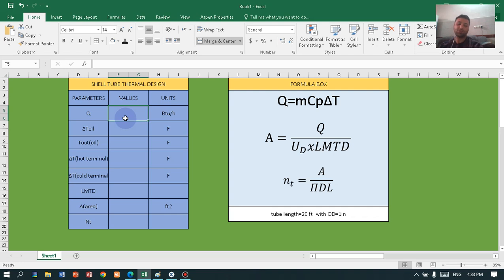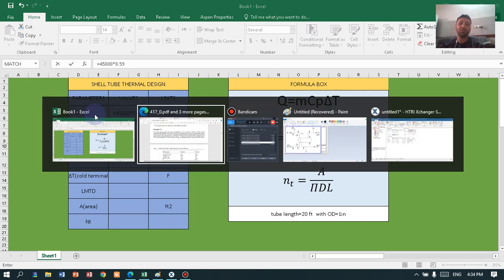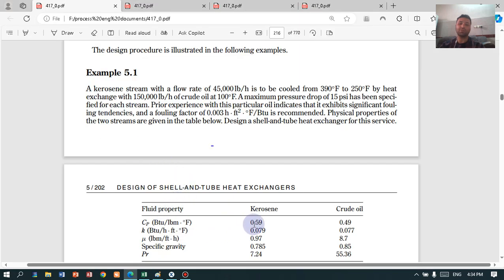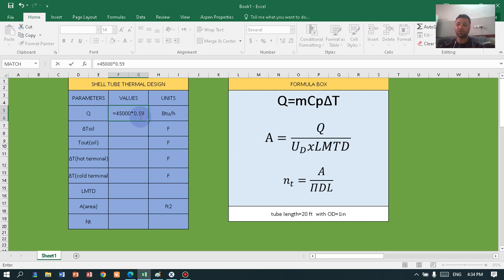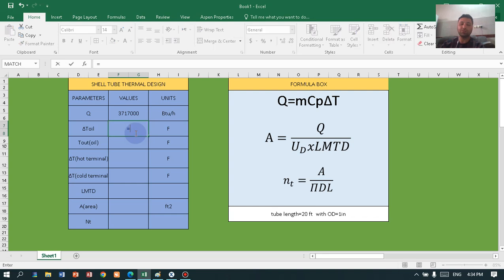Press equal to start calculating the heat load. Insert the mass flow rate on the shell side, multiply by 0.59 because the kerosene heat capacity is 0.59, and multiply by the differential temperature — open bracket — 390 minus 250 for the shell side. Close the bracket and we have the heat load.